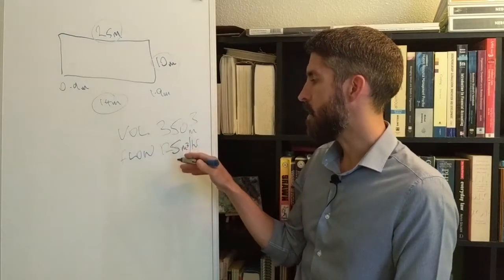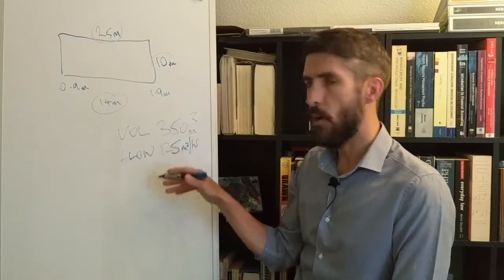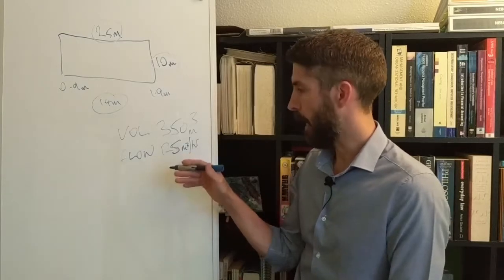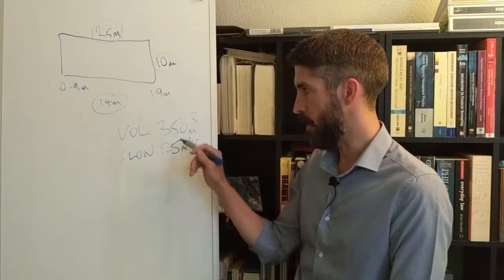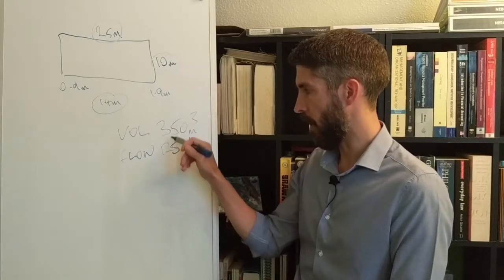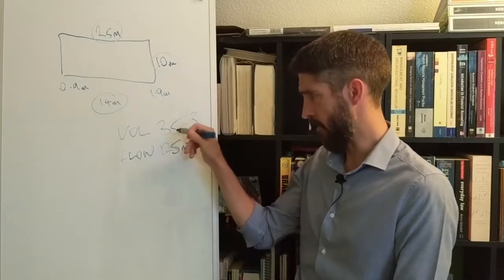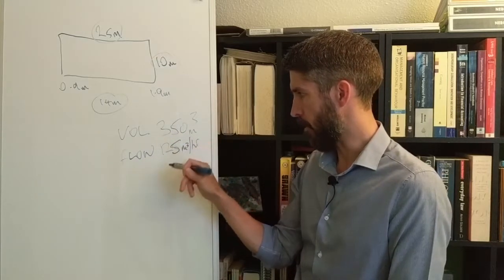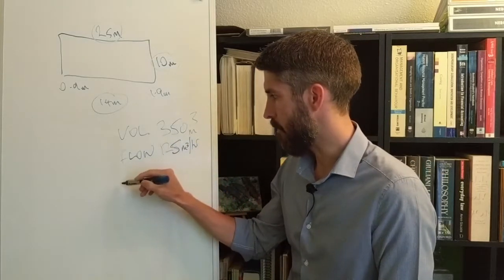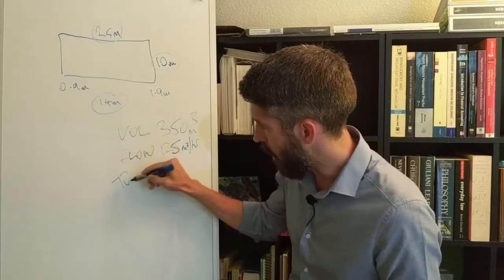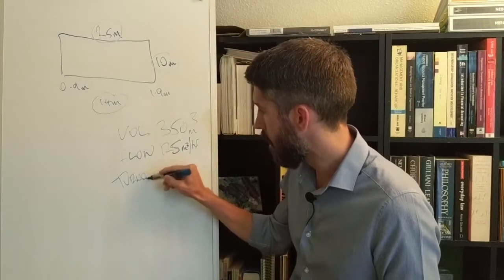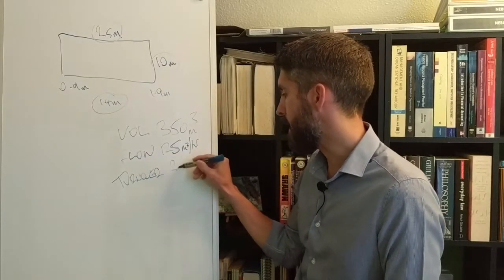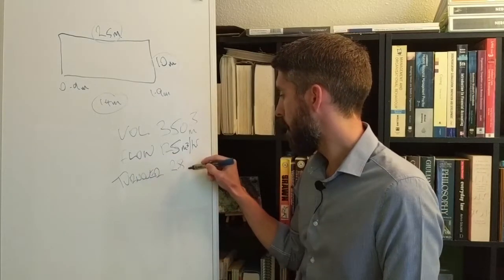What you do is once you know your volume and you know your flow rate, you've got the information you need now in order to work out the turnover time. All you do is you divide the one by the other. So 350 cubic meters divided by 125 cubic meters per hour would give you a turnover of 2.8 hours.